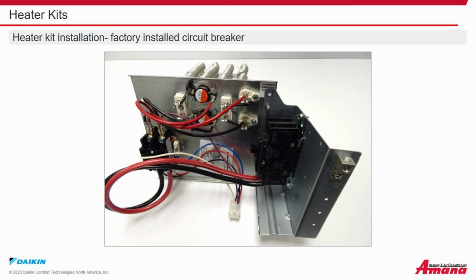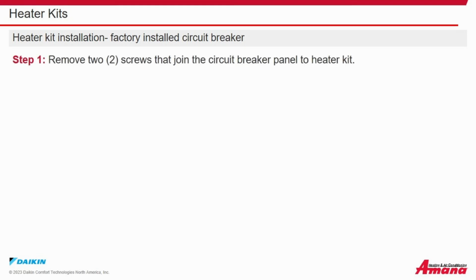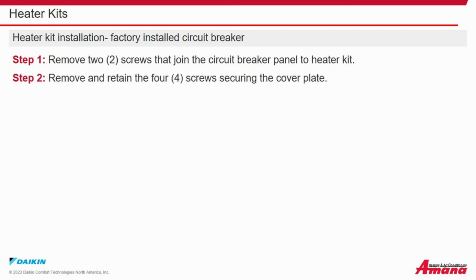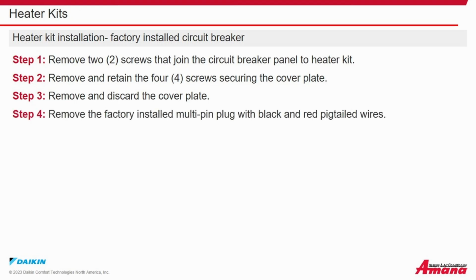Heater kit installation with the factory-installed circuit breaker. Follow these steps when installing the heater kit. Step 1. Remove the 2 screws that join the circuit breaker panel to the heater kit. Step 2. Remove and keep the 4 screws securing the cover plate. Step 3. Remove and discard the cover plate. Step 4. Remove the factory-installed multi-pin plug with the black and red pigtailed wires.